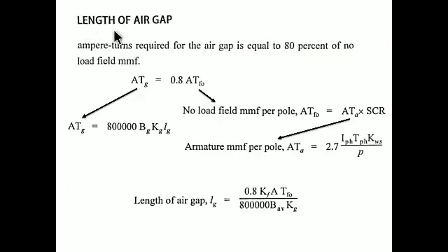Yeah, one last consideration is the air gap value, the length of the air gap. Here the length of the air gap is predicted by some basic simplification. First of all, it is calculated by ampere turns. The ampere turns required for the air gap is equal to 80% of the no load field MMF. So the equation should be written on this content.